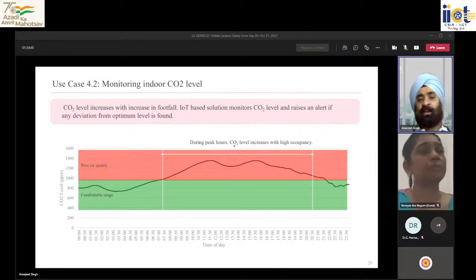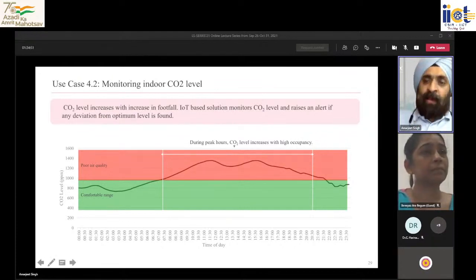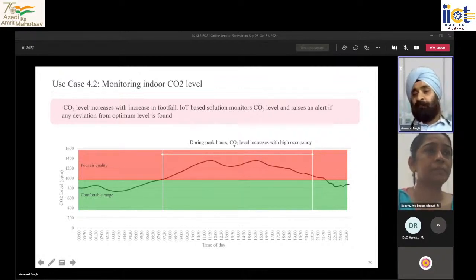So this is looking at the CO2 indicator in the building, and in several cases, based on this, if the CO2 level is going high, we would switch on the TFA, the treated fresh air unit. Rather than just recirculating the indoor air, we would bring in fresh air from outside, cool it in summer or warm it in winter, and circulate that treated fresh air rather than just recirculating indoor air, to maintain better CO2 levels.